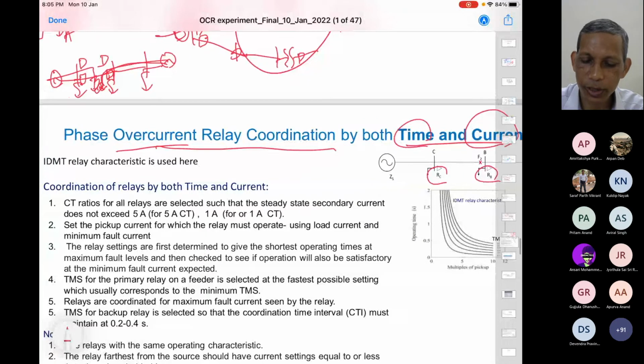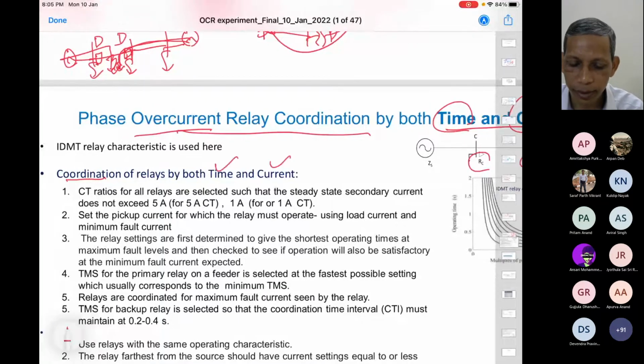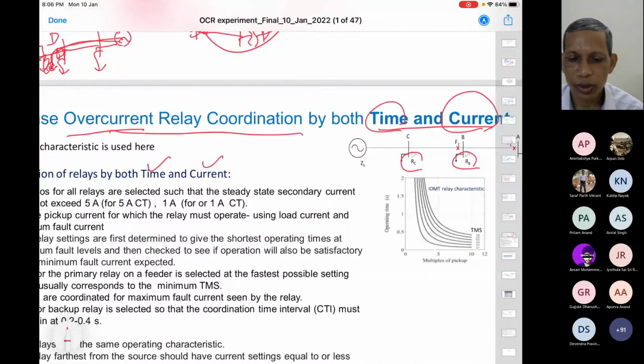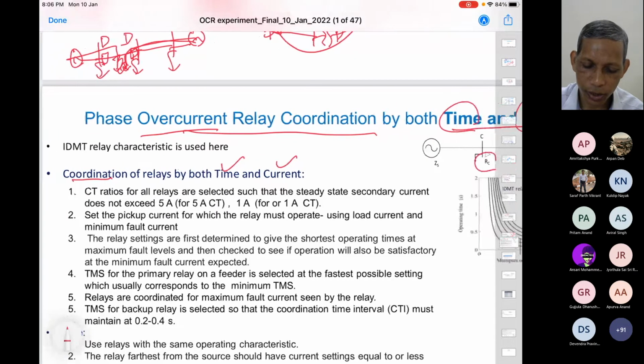So for the phase, and then similarly you can go to the ground protection. How the coordination will be achieved, that we would like to see. What are the guidelines for that, and how we will do that. So two things we have to see: time and the pickup setting. Time means time multiplier setting, TMS, and current means pickup setting. These are settings related to the characteristics. And this is about the characteristics. Either we pick IDMT: very inverse, extremely inverse, or moderately inverse, out of these three.